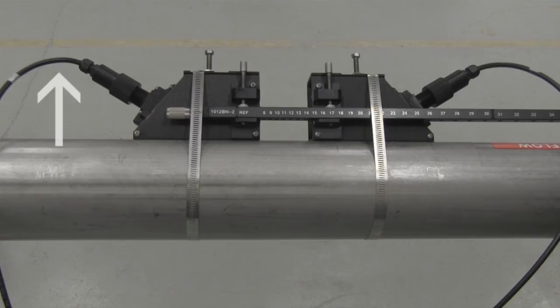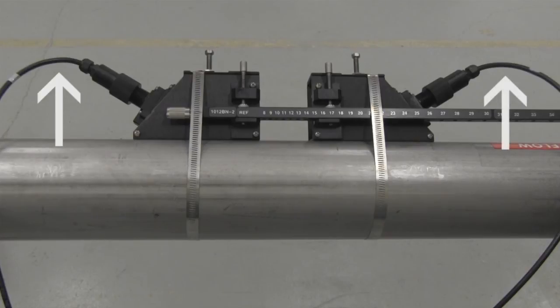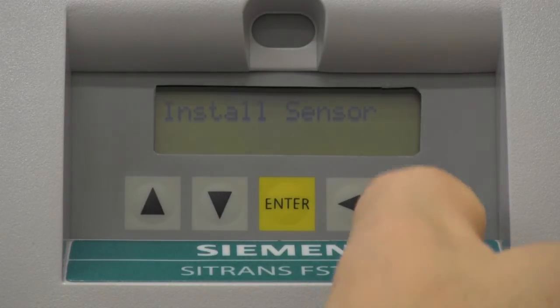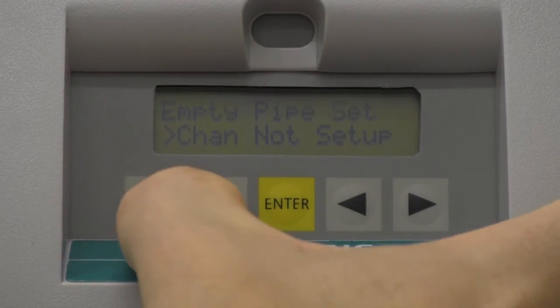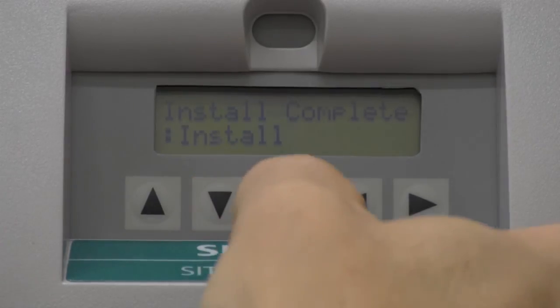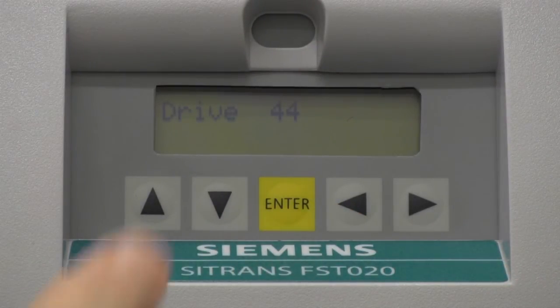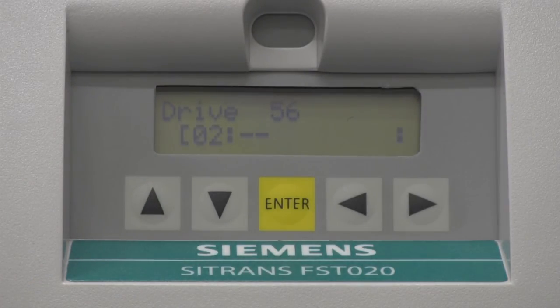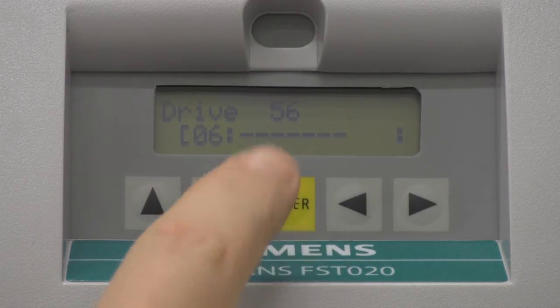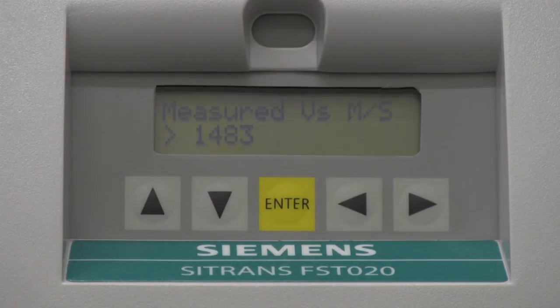Finally, attach the cable marked 'up' to the upstream sensor and the cable marked 'down' to the downstream sensor. We are now ready for the final step in commissioning the Sitrans FST020. Return to the Install Sensor screen, navigate to the Install Complete option, and select Install. The FSTO20 will display a series of drive numbers while it scans for the optimal sensor frequency. Once the frequency has been selected, a bar graph will be displayed as the operating parameters are verified. Upon completion of the initial make-up, the FST020 will display the measured sonic velocity for your liquid.